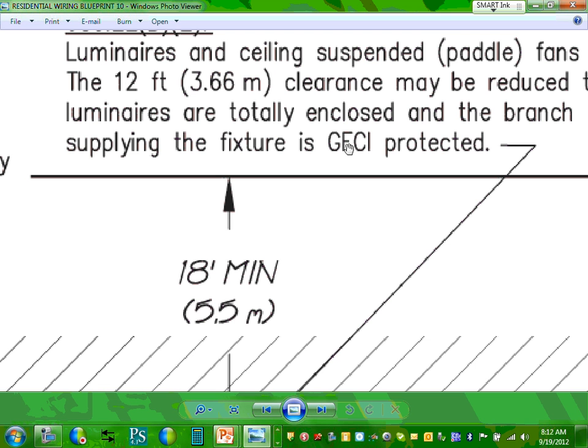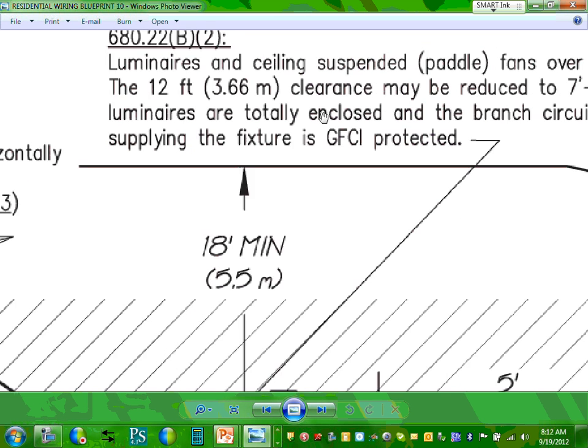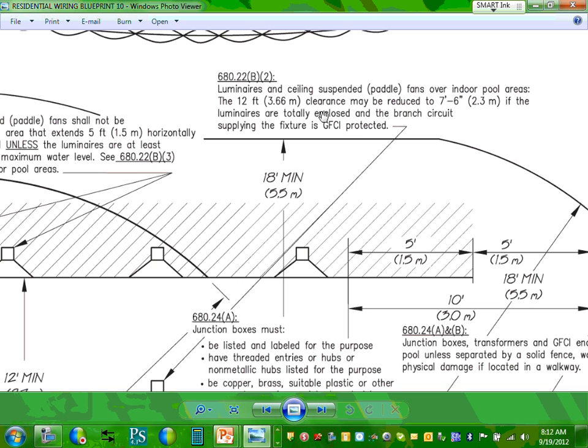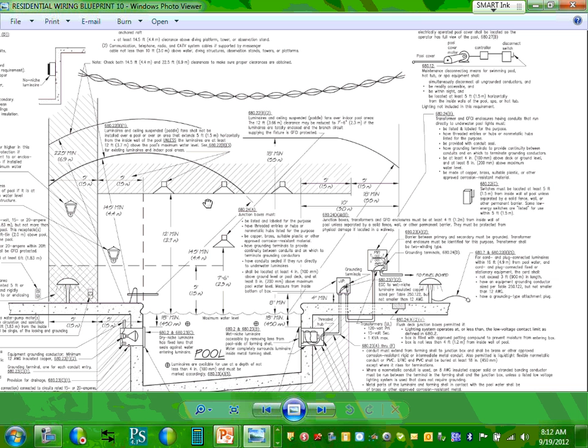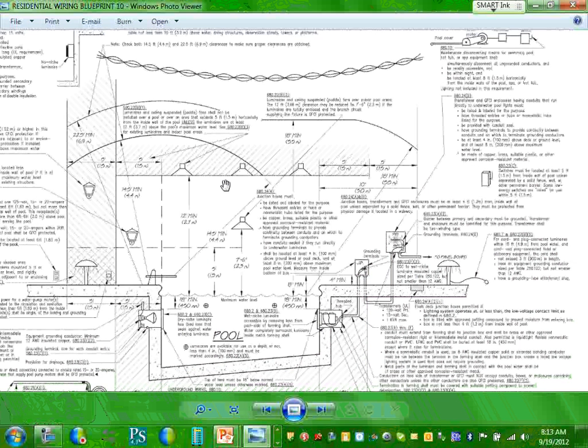GFCI. So the rule is, if you put a light above the swimming pool, what's the rule there? Not closer than 12 feet. But if you have an indoor swimming pool and the ceiling is lower than 12 feet, what do you need to do? Then you have to have a listed fixture for wet location, and you GFCI the circuit. And you can't put it closer than what? No matter what you do, you can't put it closer than 7.6. Can I have thumbs up, Chad? We understand how to put it. We're not putting lights above the swimming pool, guys, in our case. So our swimming pool, we're going to end up putting basically pole-mounted lights.